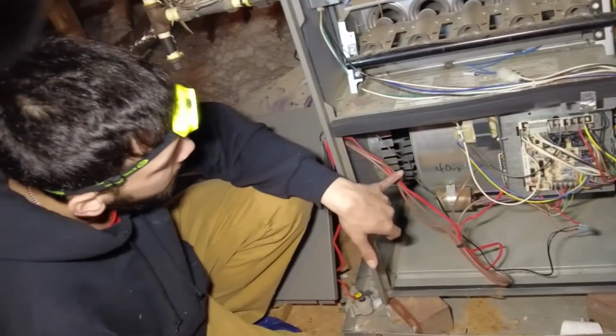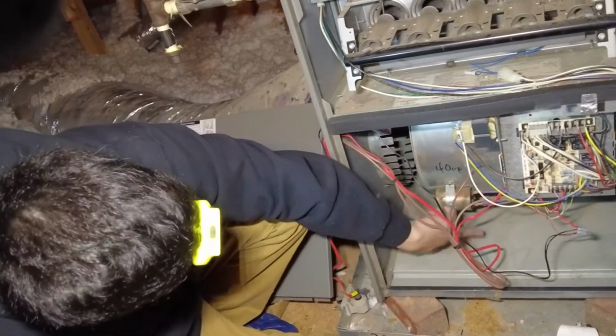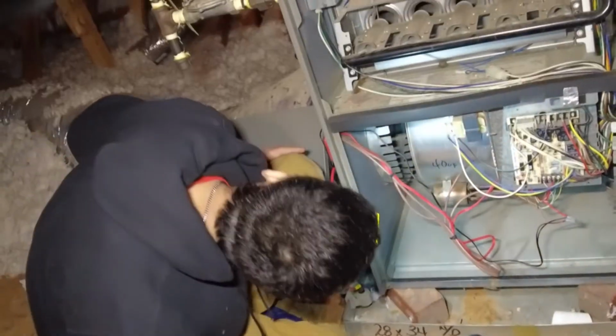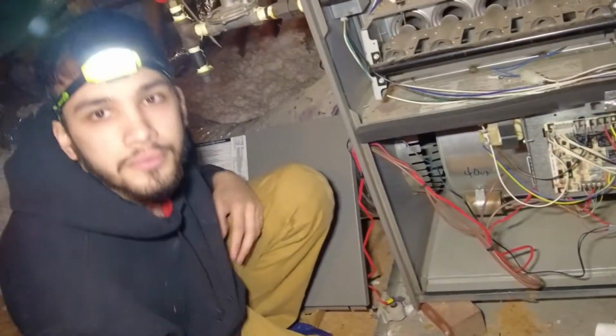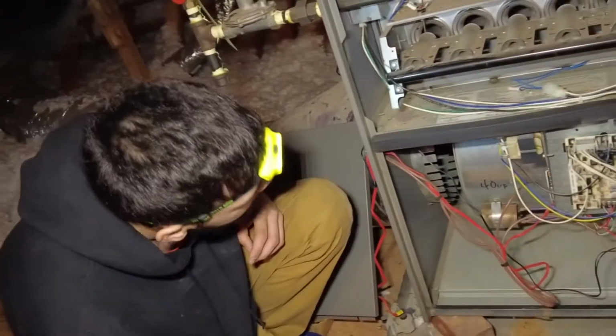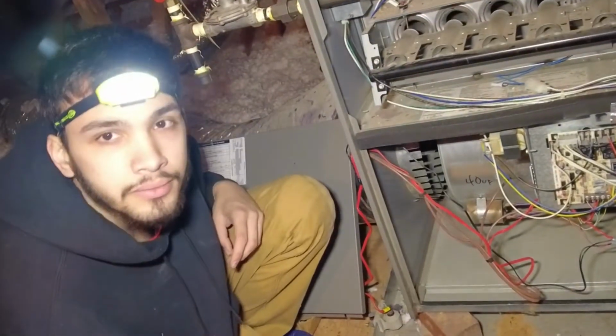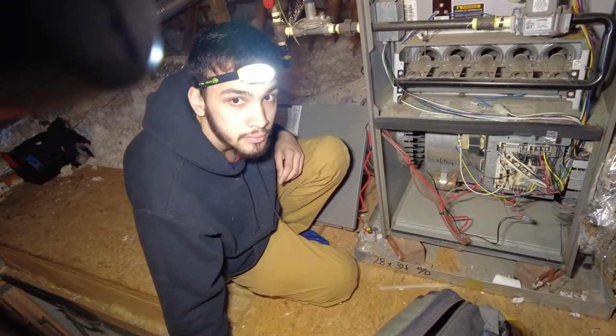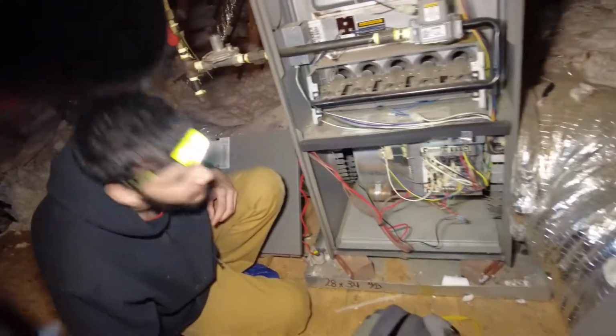Exactly, she's solid. What typically causes something like this to go bad, the blower motor? Yeah, it's getting run by this little bitty capacitor right here. Usually the internal windings fail, they could overheat. Or you've got also, I've seen plenty of them where the motor itself just locks up, essentially, just due to the bearings failing. I'm going to cut it back on. So it's all kind of mechanical stuff within the part itself.